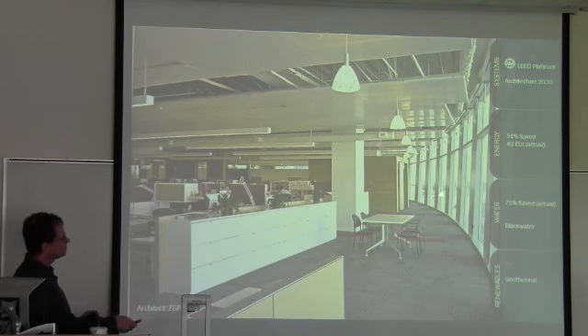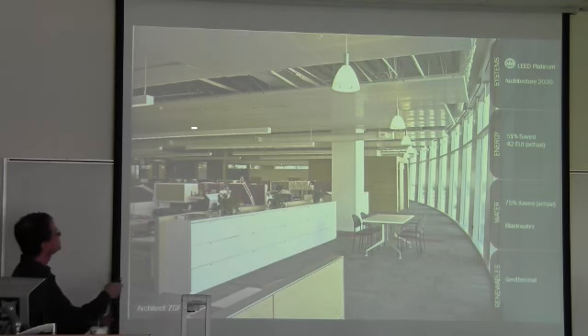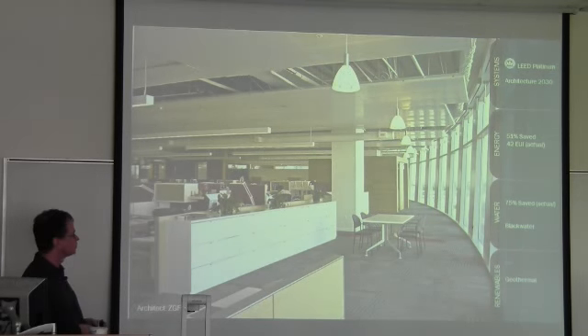This is that curtain wall system to the north, so you can see the floor-to-ceiling glass. And everybody in the space that works back here has that view, so it's a very good environment. They're getting a lot of their conditioning from the radiant panels. I was out there on a 28-degree day, and the radiant panel was measuring 75 degrees. It was barely heating. So the system runs great.